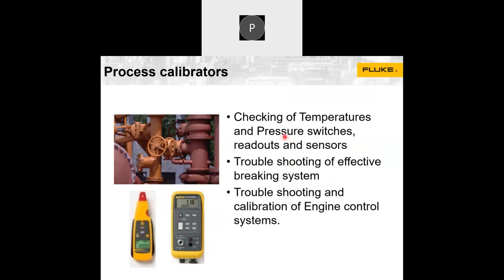Then comes process tools, which is a simple thing that may not be of much use to you, but checking of temperature and pressure switches or readouts and sensors, troubleshooting of braking systems, or troubleshooting of calibration of engine control systems, or even some activation actuators used in older types of signaling systems. You may have mechanical arms controlled through sensors. In those conditions, if you want to find out whether those sensors are functioning or giving the exact 4 to 20 milliamps or some voltage levels, you can use this kind of tester - handy but very precise devices which can source or measure these tiny voltages and currents.